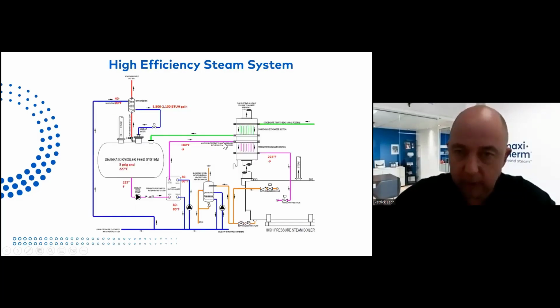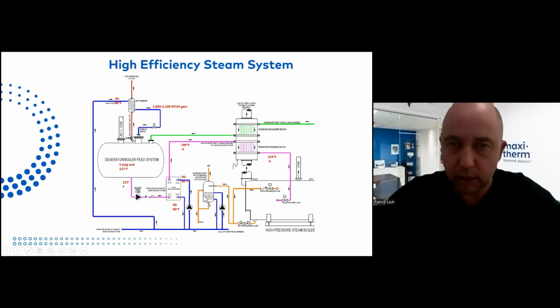And from the DA, we're going here to a normal stack economizer. And you've got all those heat recoveries if needed. Because if it's 100% closed loop, you don't need a deaerator anymore. You will need a deaerator if you have a big load of steam injection, such as humidification, sterilization, and others. But depending, talk with your water treatment guys, depending on the load, max load, you might not need a deaerator anymore. And like I said, 100% closed loop.